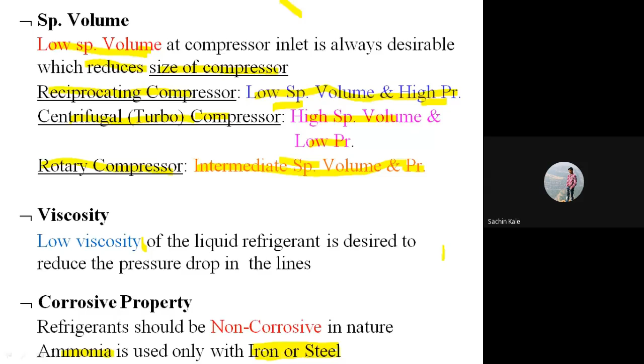If you are going to consider ammonia, a very important point for the aptitude. Whenever you are choosing ammonia as a refrigerant, then whatever refrigeration system will be there will be made up only of iron or steel. Apart from iron and steel, if you make that refrigeration system using copper or any other material with ammonia, then ammonia will be corrosive with any material apart from iron and steel. So whenever you are using ammonia as a refrigerant, by hook or crook you have to use iron or steel for manufacturing that refrigeration system. Are you getting?